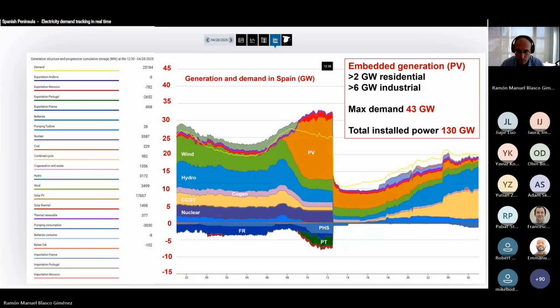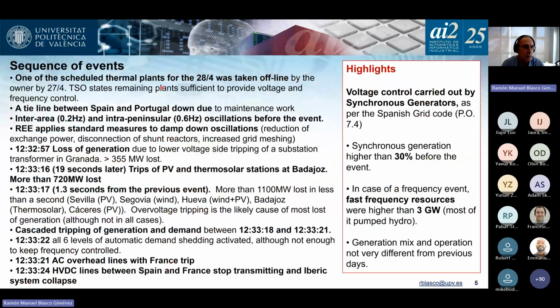What's the sequence of events? The sequence of events is prior to the event. So the day before, there were several thermal plants scheduled. Thermal plants, just to give you an idea, in Spain, by the Spanish grid code, PV and wind operate on constant Q or operate on constant power factor. So they don't participate on dynamic voltage control.